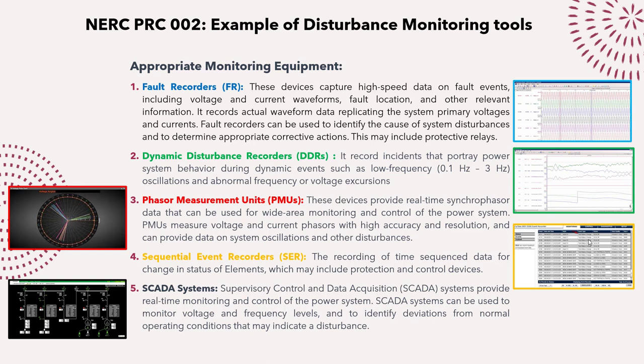Dynamic disturbance recorders capture incidents that portray power system behavior during dynamic events such as low-frequency oscillations and abnormal frequency or voltage excursions. Phasor measurement units provide real-time synchrophasor data for wide-area monitoring and control of the power system. PMUs measure voltage and current phasors at very high accuracy and resolution, allowing monitoring of angular separation across the power system and providing a complete dynamic overview of the entire system — showing how generators, loads, and all elements behave dynamically during faults or disturbances.